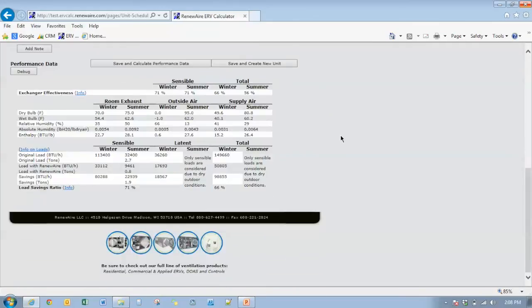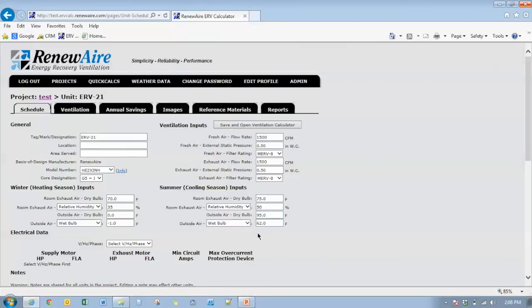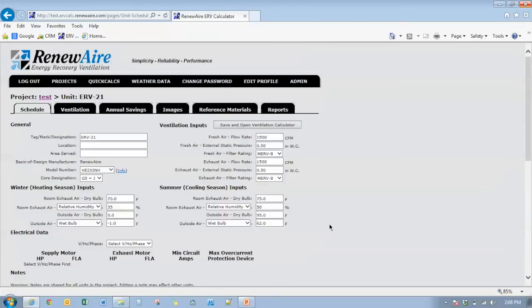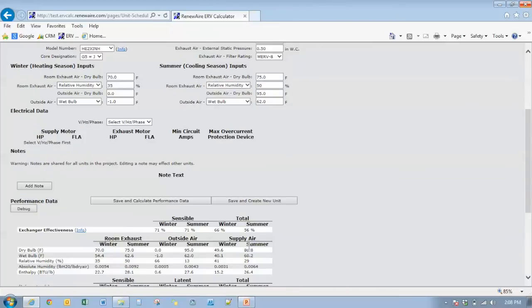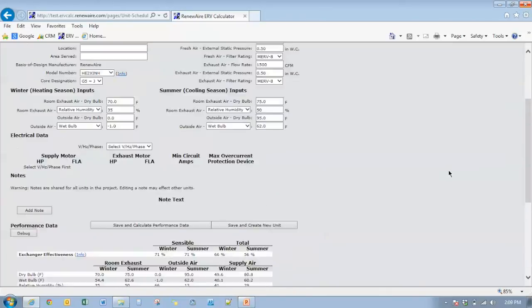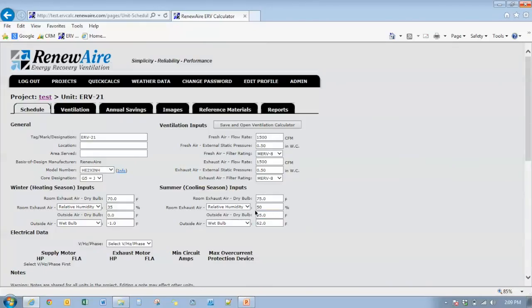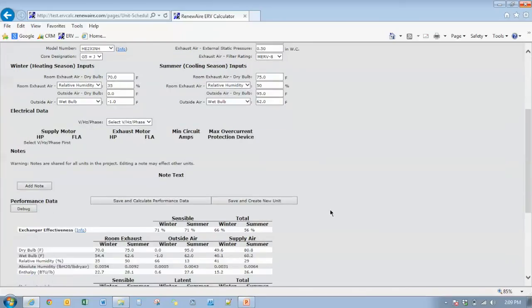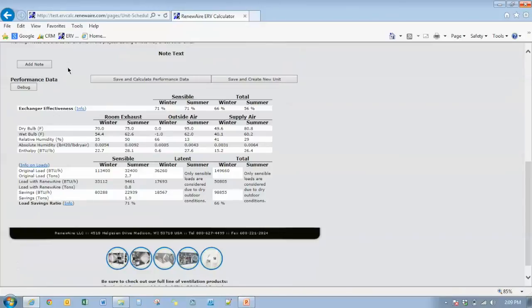When we have drier outside air conditions than we have inside conditions, the load actually turns into a humidification load as opposed to a dehumidification load as would be typical. Consequently, when we do the load calculations, those loads come out to be negative loads. Most often those loads don't get incorporated into the building. They're just looking at the sensible load recovery of that outside air that's coming in.